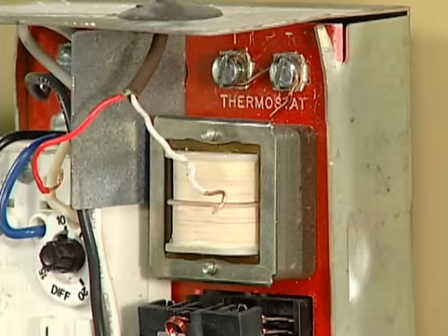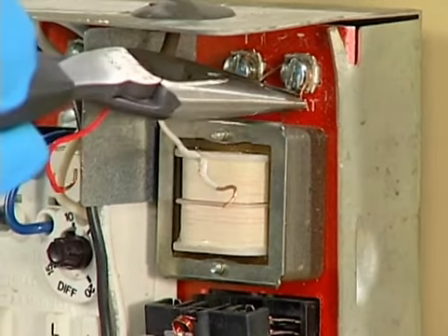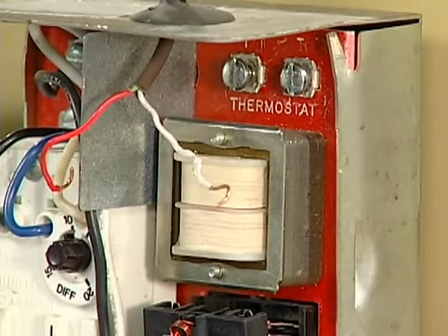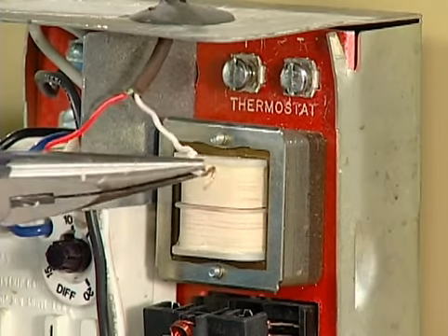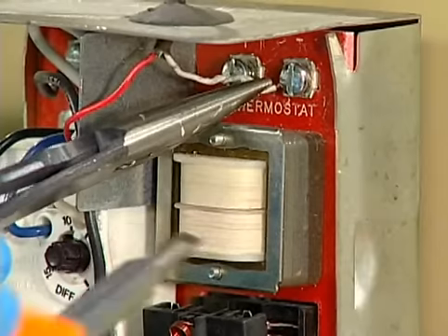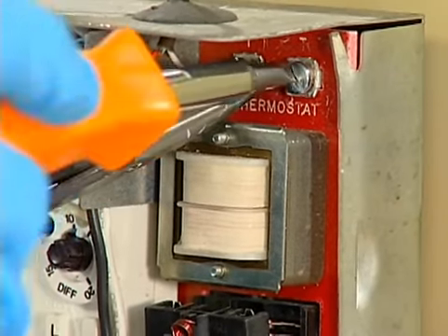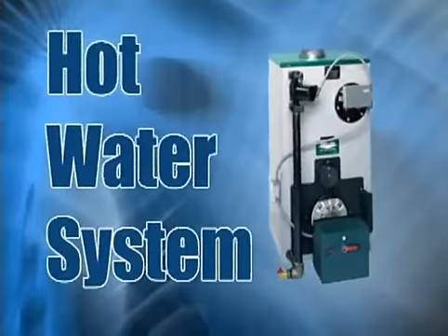To test them, you should first remove your jumper from the TT terminals and replace the thermostat wiring. If there is more than one thermostat, make sure each is set 10 degrees above room temperature.